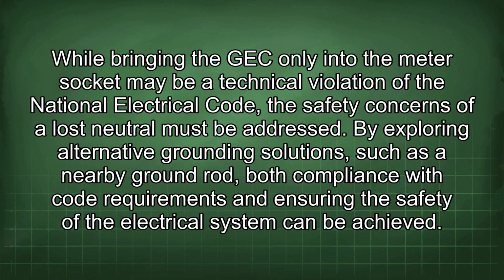While bringing the GEC only into the meter socket may be a technical violation of the National Electrical Code, the safety concerns of a lost neutral must be addressed. By exploring alternative grounding solutions, such as a nearby ground rod, both compliance with code requirements and ensuring the safety of the electrical system can be achieved.